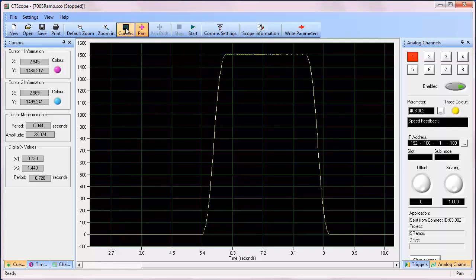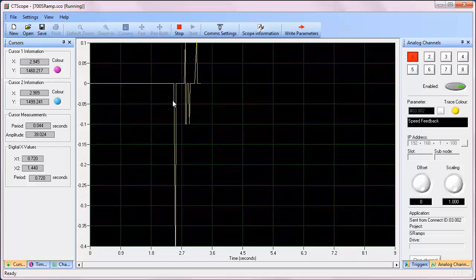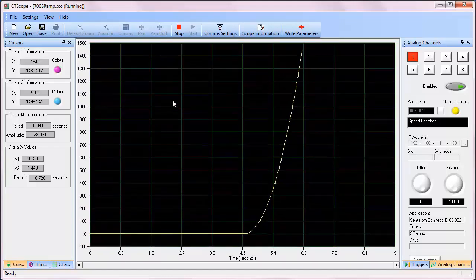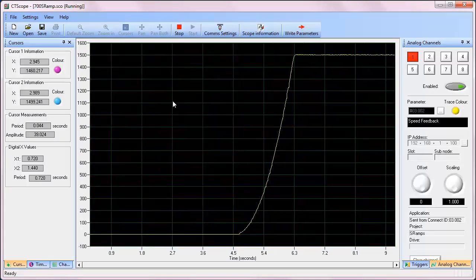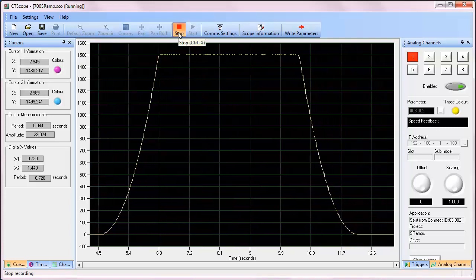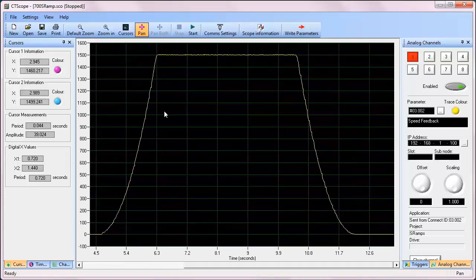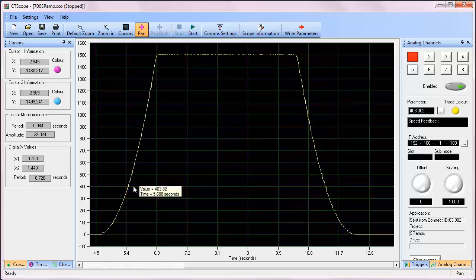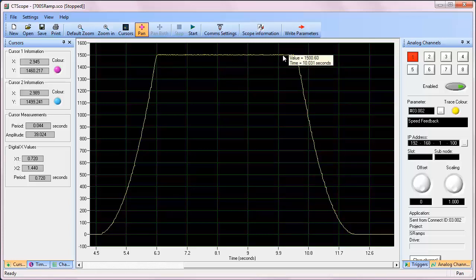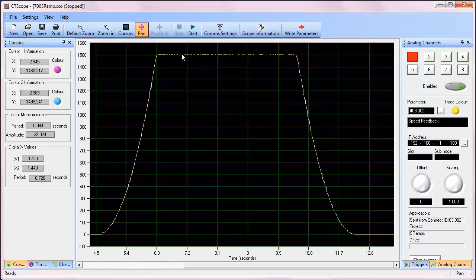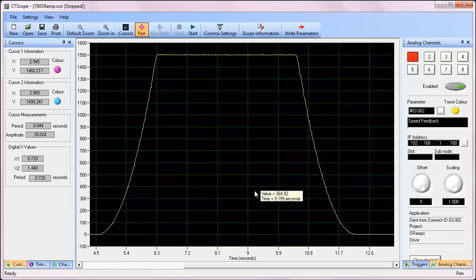All right, so I'm going to start my trace and let's run it. See what that did? The S is applied during the first transition. But up here, once we're up to speed, there is no S here. And when we begin accelerating in the negative direction or decelerating, there's very, very little of an S on those transitions. And then the S is again repeated on the end. So that is the independent mode of operation for S ramps.